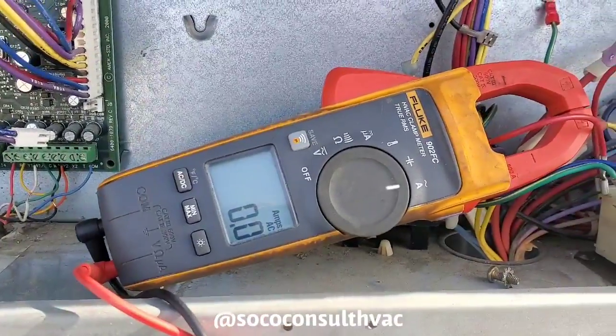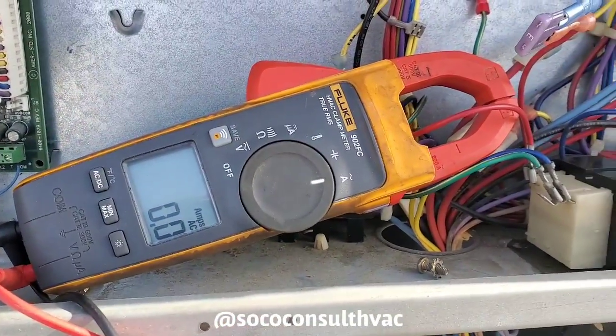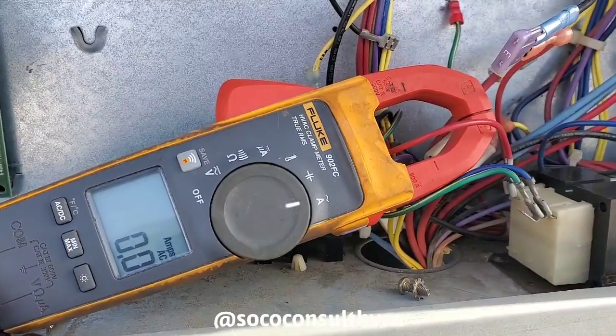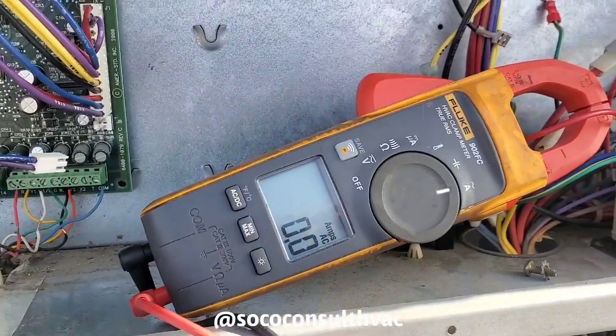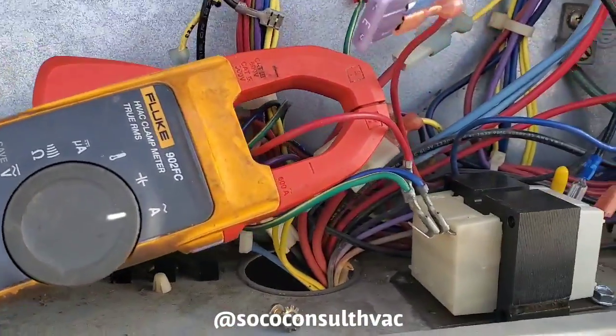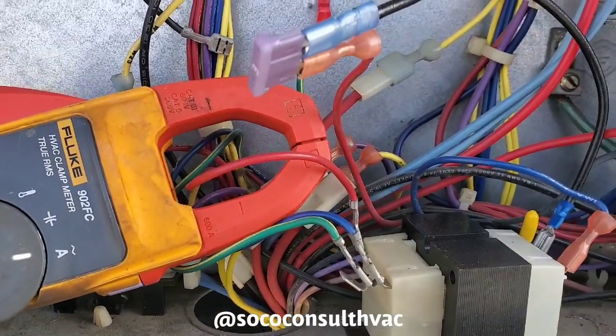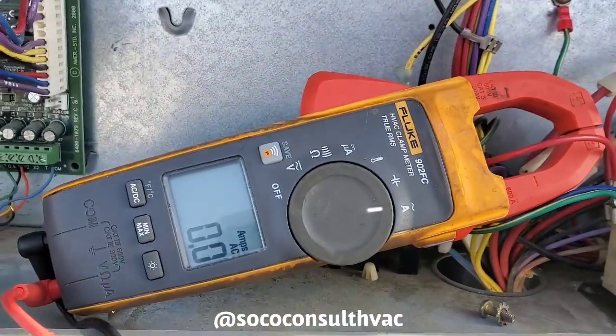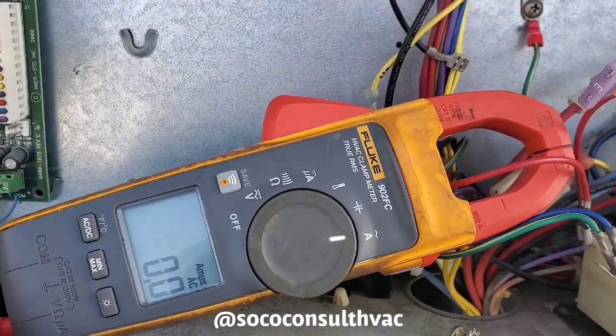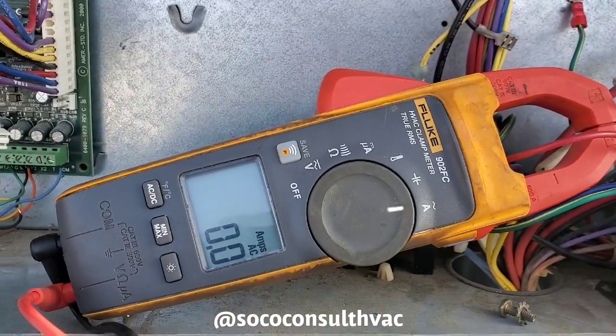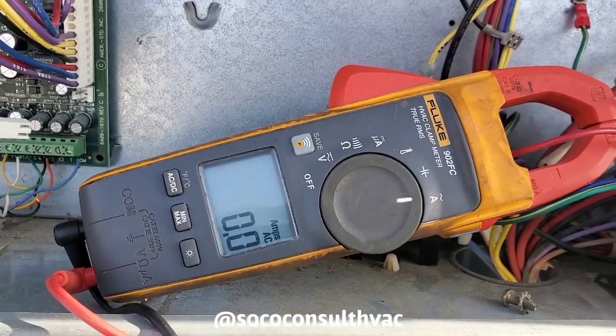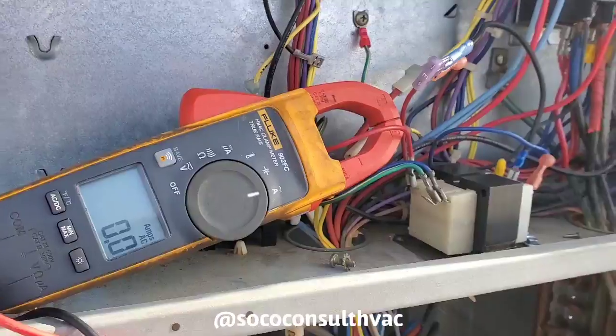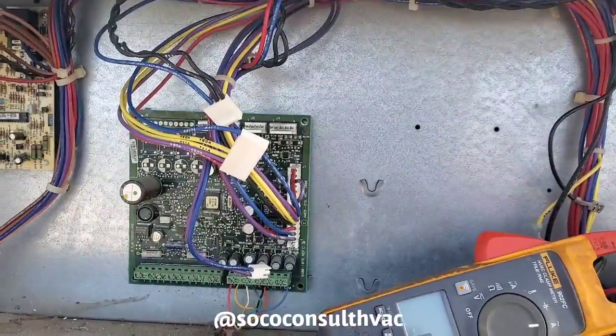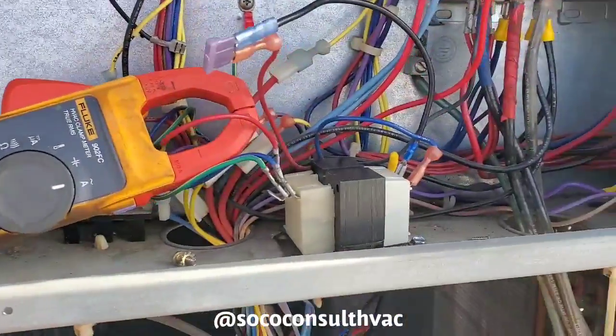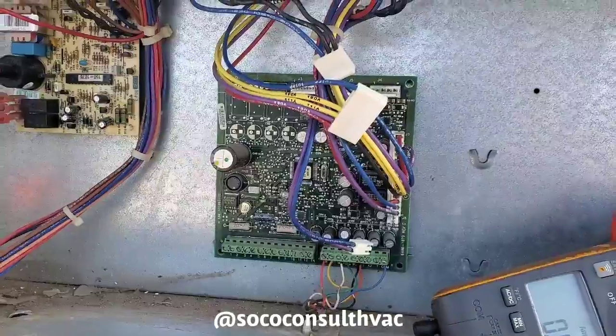So that I don't go through a bunch of fuses, you can either use one of those clip-on circuit breakers. Those aren't always reliable. Me personally, I put my amp clamp around the red wire, or whatever 24 volt hot wire, and I monitor that, and anything over about an amp or two, I'm going to kill the power, because that means I have a short. And that's actually a quicker way of determining a short than waiting on a fuse or a circuit breaker to finally blow and risk blowing a brand new transformer.